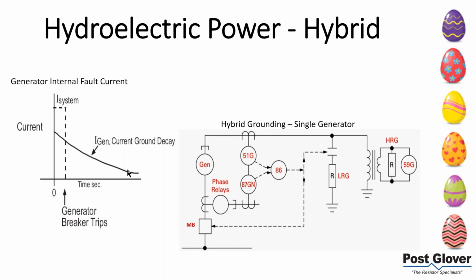And this actually causes, there are a couple of white papers on this that go into detail, a lot more damage than you would expect. But essentially this causes additional damage. So a hybrid application would rectify that issue. I bring this up because this is ideal for medium voltage generators, and could very well be a good application for your hydro application. I will say this is going to be high level. Application-wise, it's very varied.